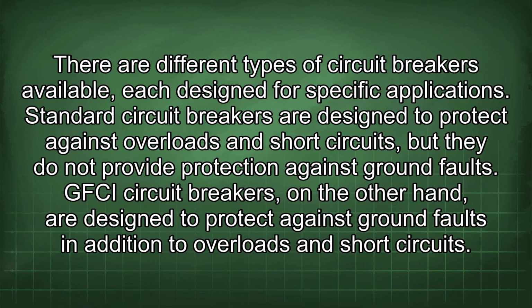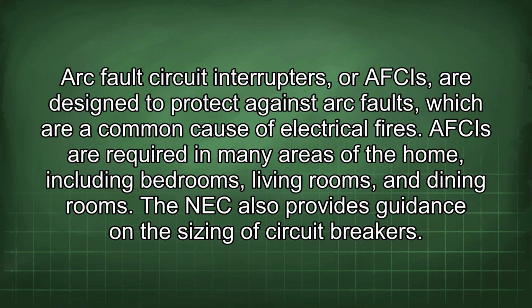faults. GFCI circuit breakers, on the other hand, are designed to protect against ground faults in addition to overloads and short circuits. Arc fault circuit interrupters, or AFCIs, are designed to protect against arc faults, which are a common cause of electrical fires. AFCIs are required in many areas of the home, including bedrooms, living rooms, and dining rooms.